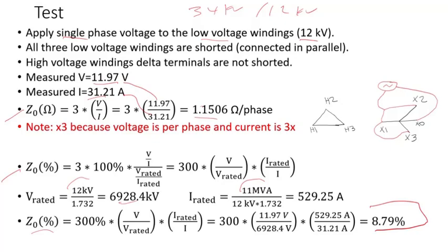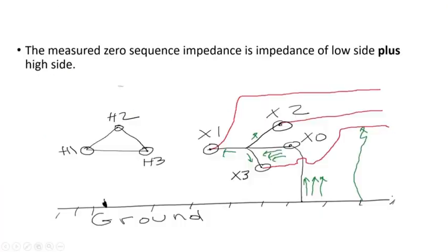Going back to the T-model: the high side (34 kV) shows the winding, but because it has no neutral or ground, it is open. Here is the Y side and here is X. From X to Y, that represents the zero sequence impedance.